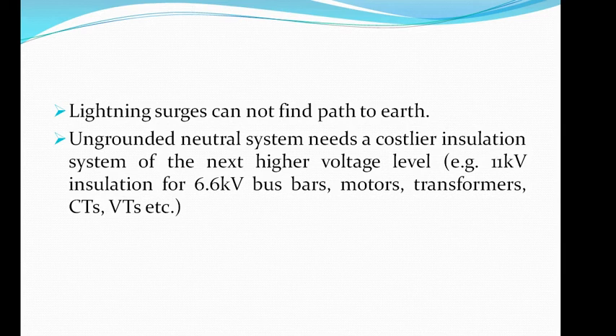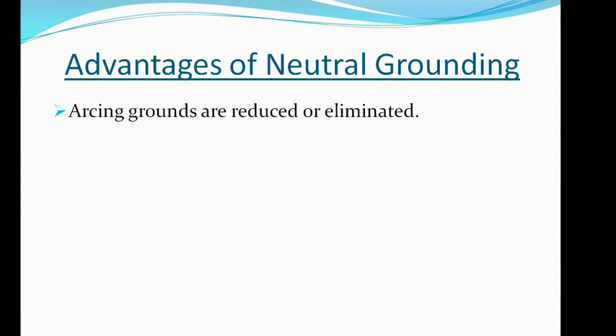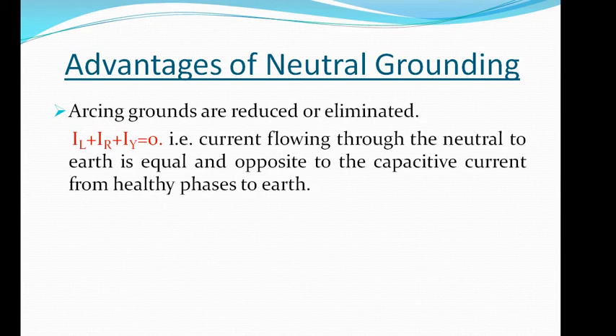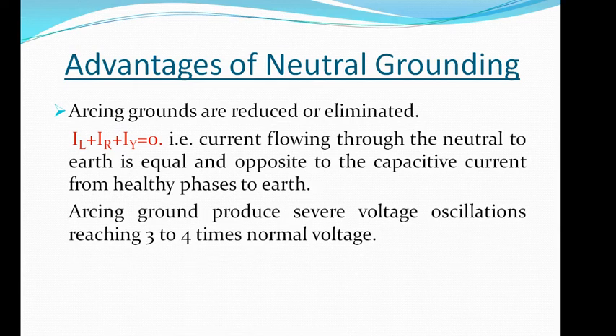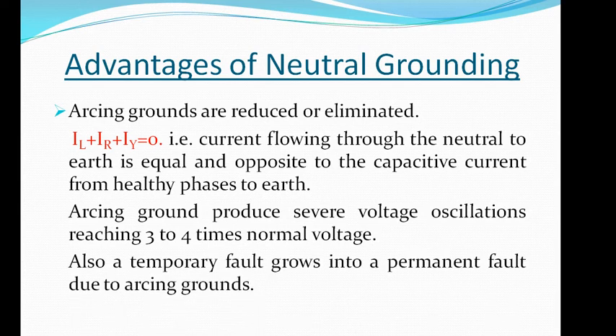Modern electrical relaying and protection systems are designed considering the simplicity and sensitivity of a grounded network. There are several advantages of a grounded system. The main advantage is that arcing grounds are reduced or can be completely eliminated in a grounded network, where iL + iR + iY = 0 — that is, the current flowing through the neutral to earth is equal and opposite to the capacitive current from healthy phases to earth.